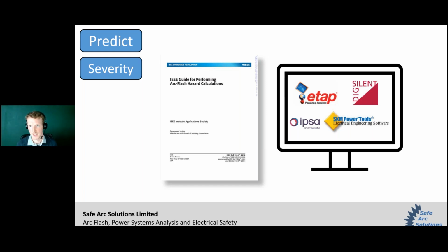It's worth mentioning that the 1584 standard does have some limitations. It only goes up to 15 kV. So this tends to be, in our experience, this covers a lot of the commercial and industrial systems out there. But if you do have a system that's operating higher than that, some equipment on site that's operating above 15 kV, there are alternative methodologies that are available to look at that.